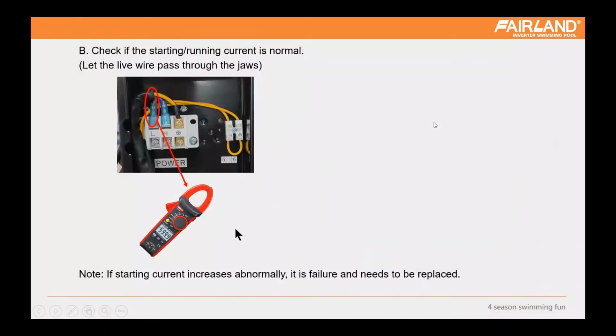If our compressor runs from 0% to 100%, at the beginning the amperage is just 1 or 1.5 amperes. It will not be so big. But if you use the clamp meter and track that the current is almost 10, then it's a problem. That means the compressor gets stuck inside, so it makes a big current.